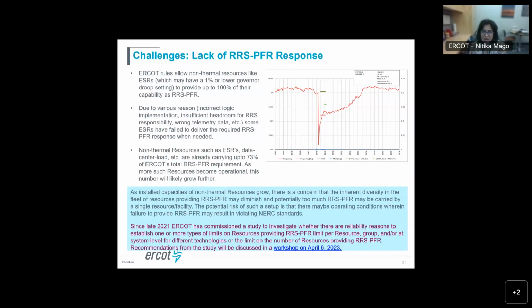Maybe I'll first focus on responsive reserve that we get from primary frequency response resources. ERCOT today has a rule which allows non-thermal resources like batteries to provide up to 100% of their capability as RRS PFR. So in order to do so, they typically end up setting their droop settings for governor response to 1% or lower.